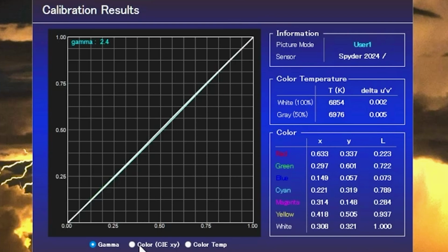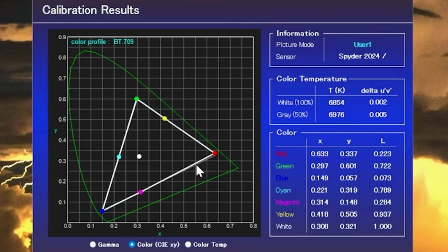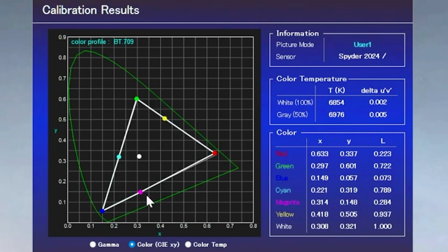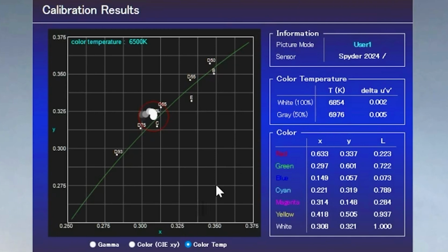If you go to color, which is the color gamut, it'll show you the profile for BT709. Again, the white is after, the spec, the Rec 709, is in pink, and before would be a light blue. This unit's been calibrated a bunch of times, so there's really no difference in what we're seeing here. And then color temp, again, it shows you the white point for D65, and we're a little bit off of that. We're at 6854. So we're off from that a little bit, and you can adjust that with the RGB gains and offsets if you need to fine tune from this point. But it gives you a really nice baseline of the projector.